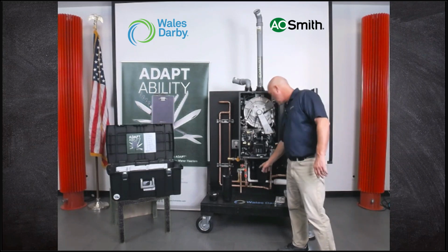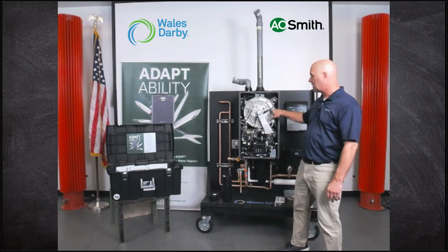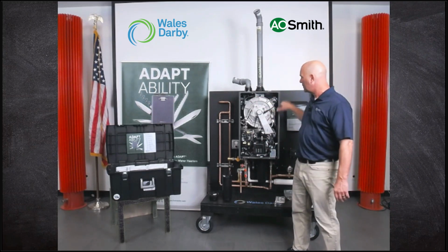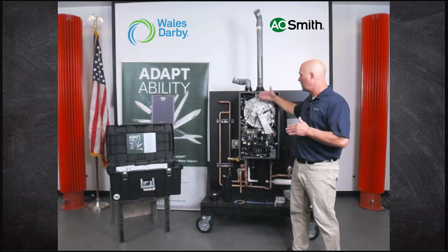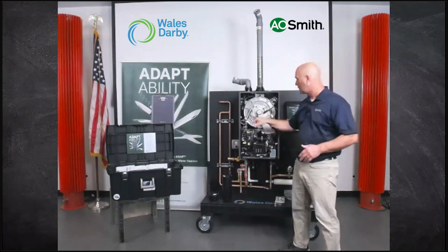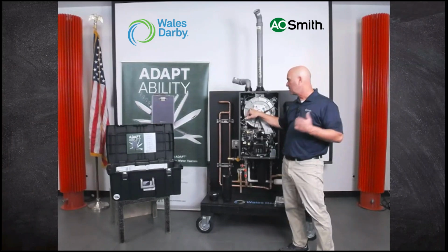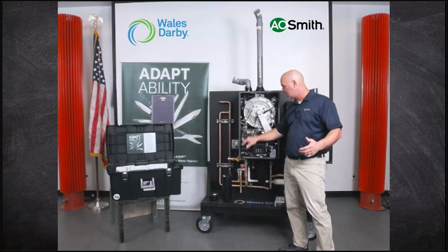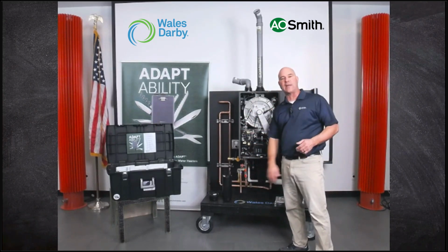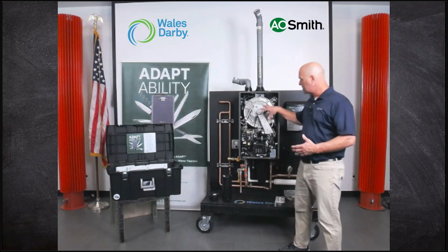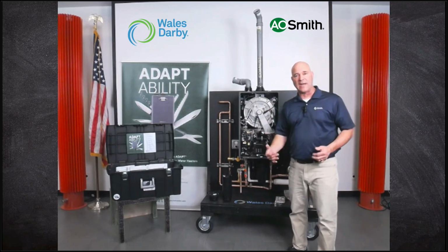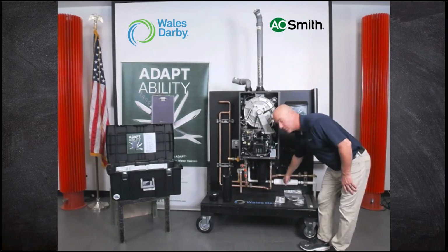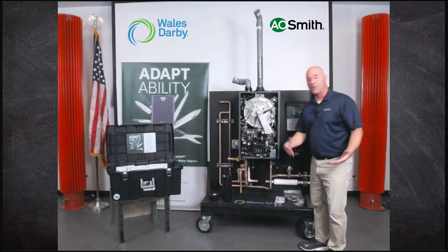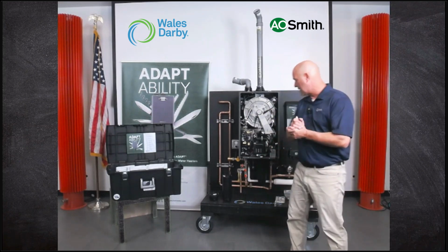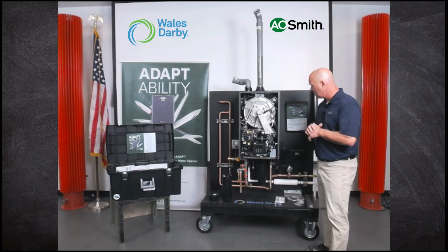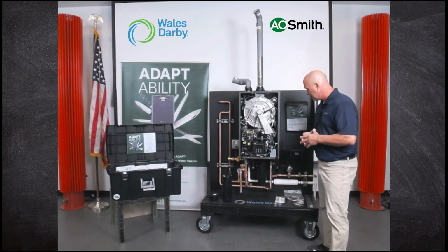So X3 cartridge goes through there, comes up, enters the heat exchanger here. It wraps from the front to the back, and then it turns around and comes from the back to the front, and we exit here, and that is your delivery temperature that we're going to take and send down and out of the 3/4 tapping on the hot side. This is a condensing piece of equipment, so we do have condensate. This unit comes down, it goes through a condensate neutralizer. You're going to want to do that. You won't want to run this into a septic tank or your town sewer. So just be aware of that.